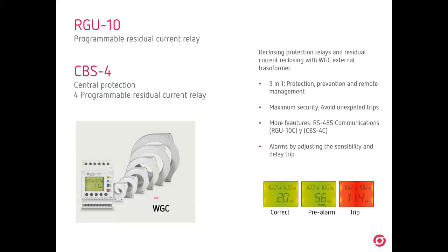So we can reclose the system. We have the ability, with the outputs, to create remote management. We can trip an MCB, for example. We can send the signal for tripping when the residual current leakage is higher than the value that we have set. We see the value on the display. The display changes to red when it is tripped. We have a pre-alarm. We have RS-485 communication, so we can connect through the EMS software. So if you are the maintenance manager and you go to the switchboard and check the relay, you will see the status, if it is green or red, so if it is tripped or not tripped.